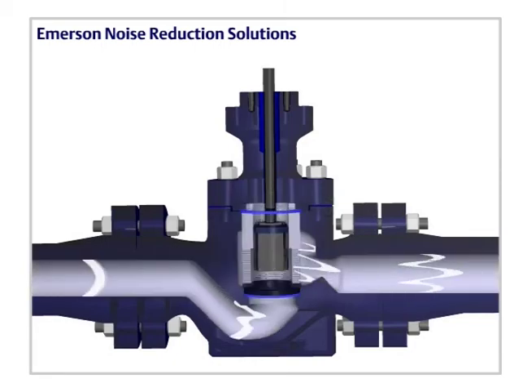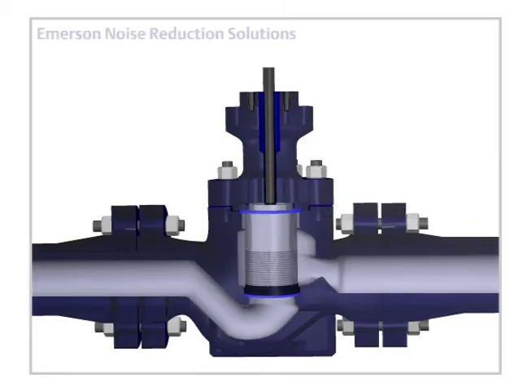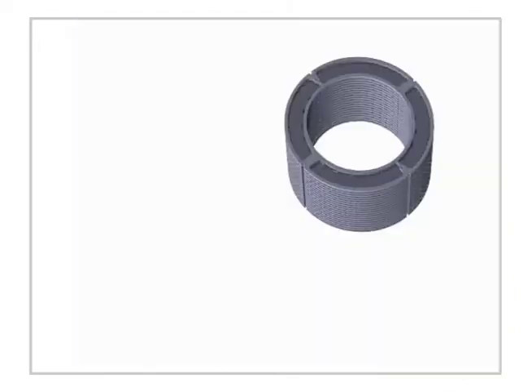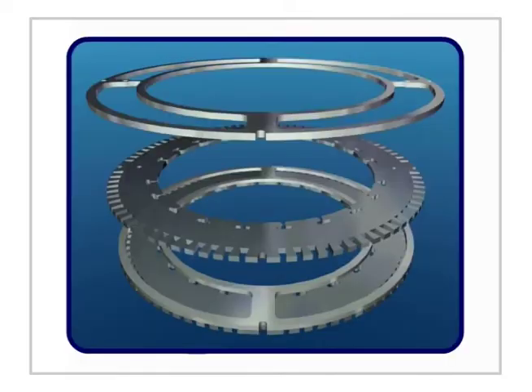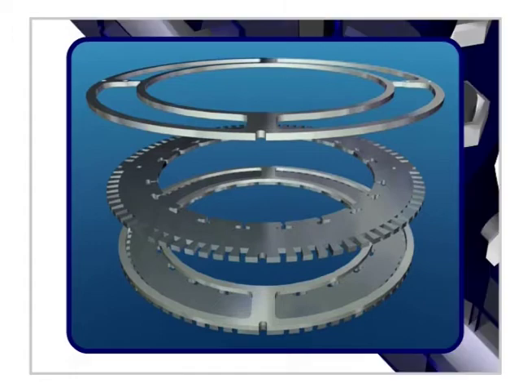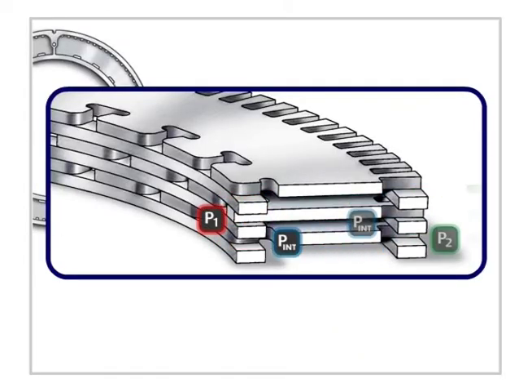Source treatments include the Fisher Whisper Trim model. Its unique passage shape reduces turbulence to minimize shock-associated noise, places turbulent shear layers away from solid boundaries to reduce dipole noise, with multi-stage pressure reduction. First stage pressure drop ratio is greater than that of the second stage.